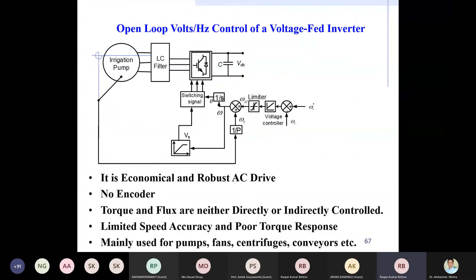V/F control is economical and robust, which is why nowadays many companies have started designing single phase inverters for pump motor drives. In this open-loop inverter control, torque and flux are neither directly nor indirectly controlled, and these are used in pumps, fans, and centrifuges.